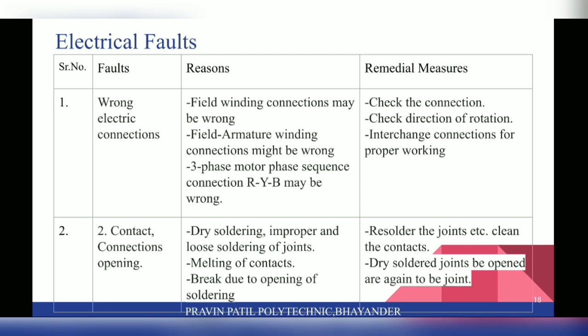Second fault is contact connections opening. The reasons are dry soldering, improper and loose soldering of joints, melting of contacts, break due to opening of soldering. And remedial measures for these faults are: resolder the joints, clean the contacts, and dry solder joints that are open are to be joined again.